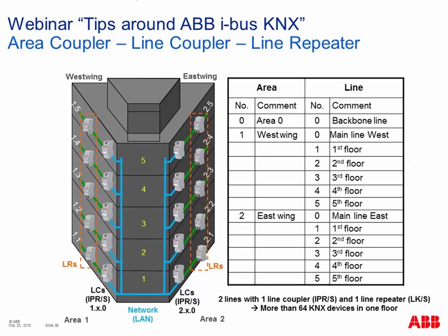Or we use the IP world, for example. Instead of twisted pair, we use our IP router, here the same 5 IP routers, and use our line repeater again. We can also install up to 3 line repeaters in parallel under one IP router, also possible.